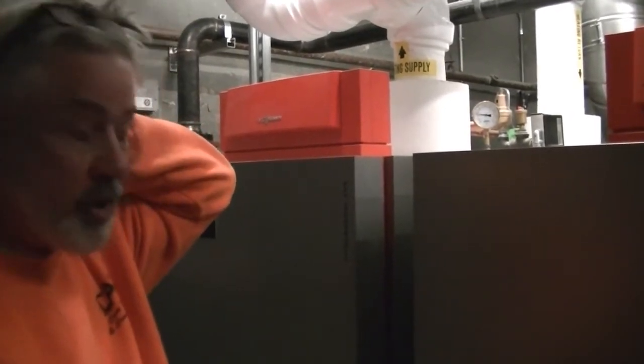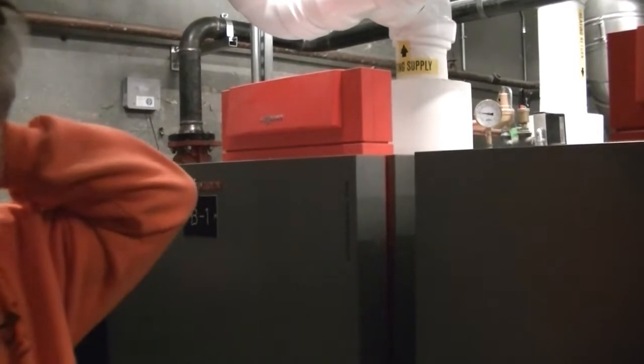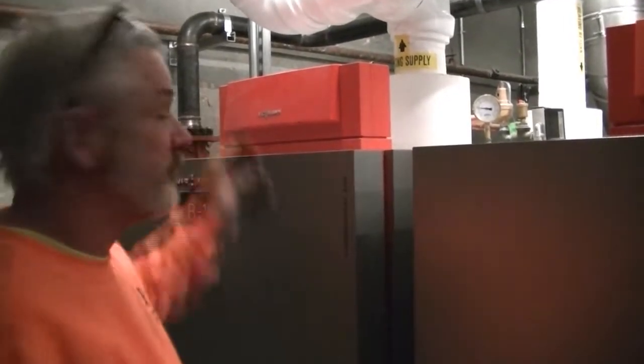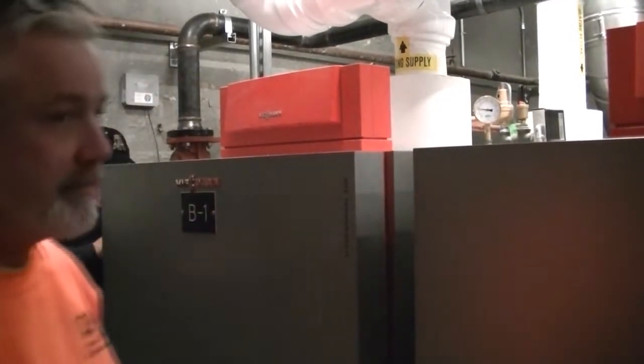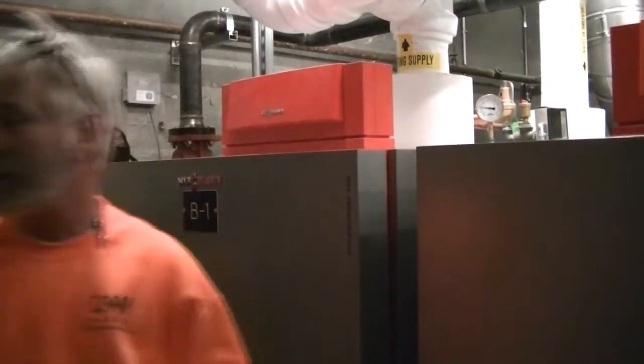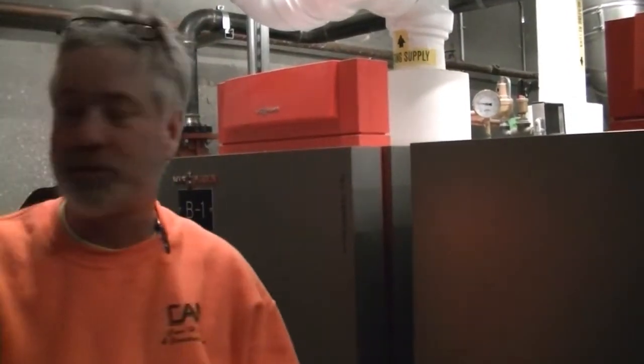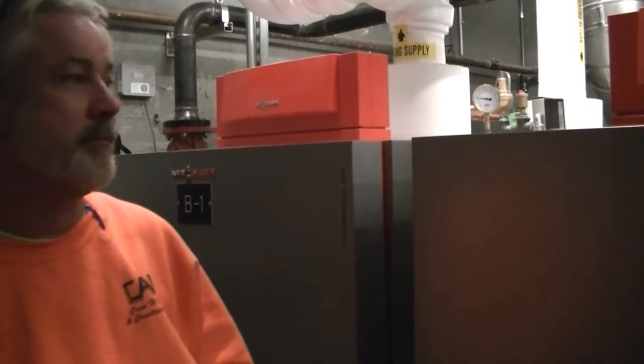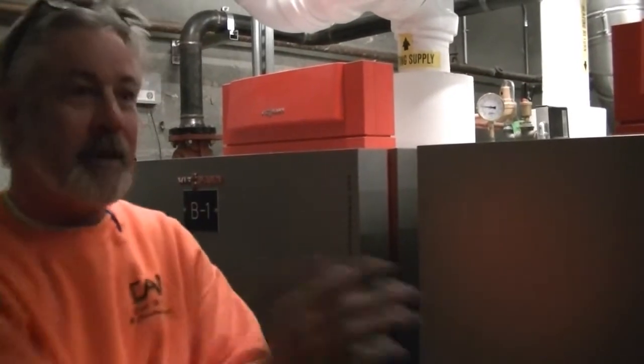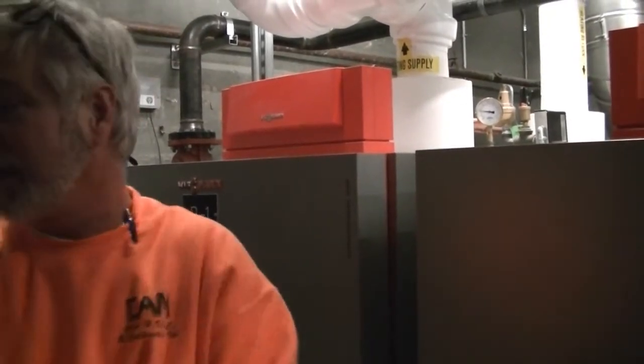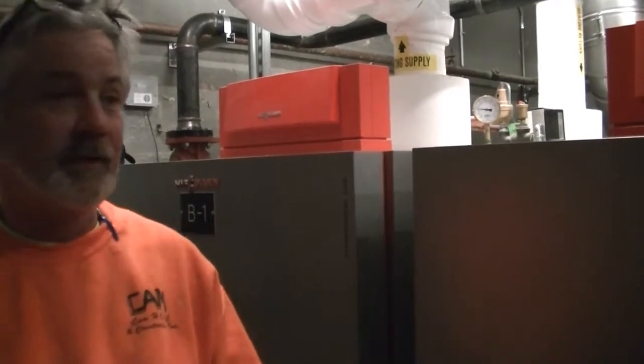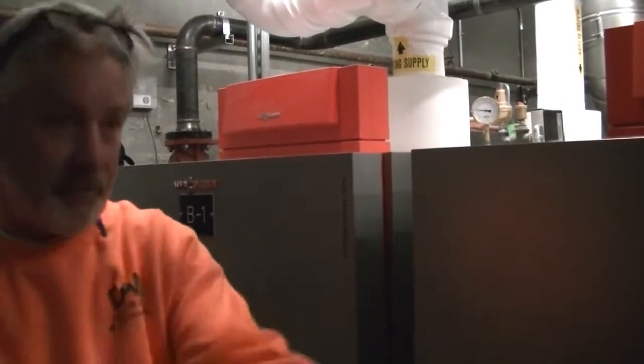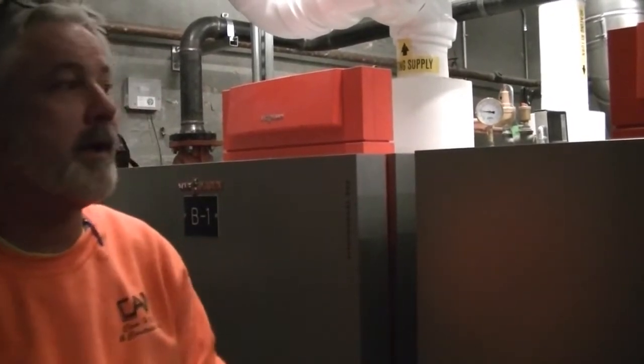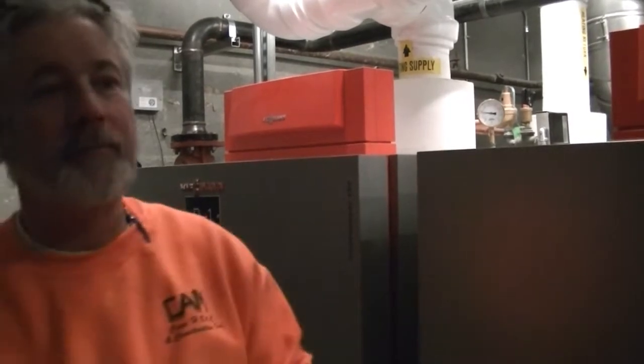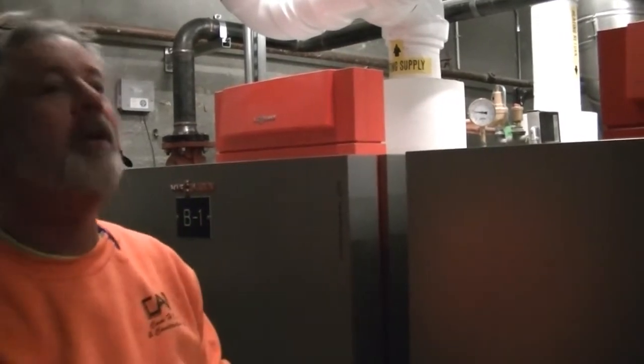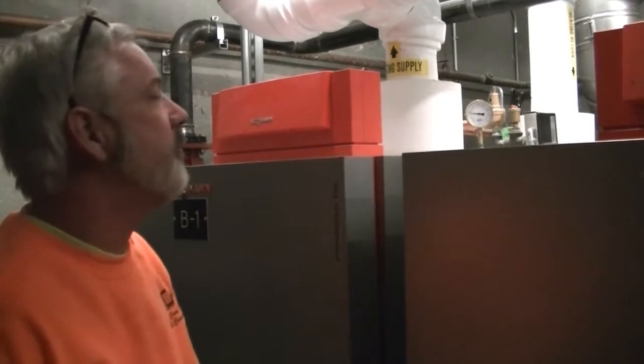Some of the things that aren't covered under the warranty are things like that. If we come up and we have to readjust things because people touch them, it's not covered under warranty. If we have to come up because somebody pushed the off button on a pump, that's operator error. If it's in auto and the pump goes bad, you're covered under the warranty, okay?